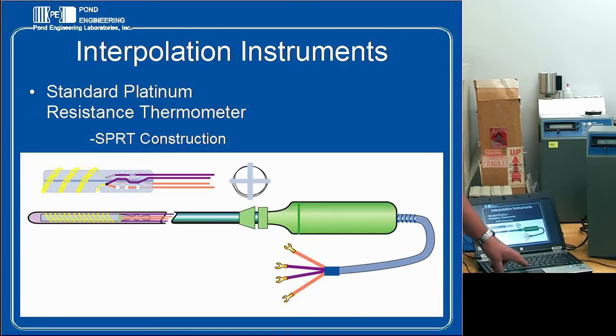And so what's the typical resistance value of an SPRT? Resistance value for most SPRTs that are used in reasonable temperature ranges is 25.5 ohms. There are high temperature SPRTs that are down in the 2.5 and even quarter ohm. Wow. So to measure that, you got to be pretty careful. You got to be. What kind of concerns do you have in trying to make a measurement on a 25 ohm resistor?